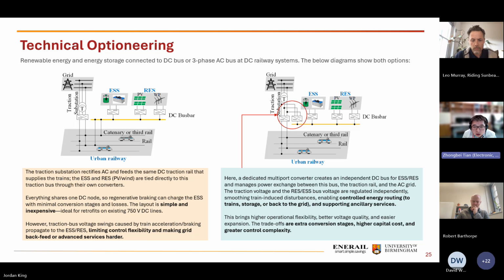The AC connection on the right-hand side can overcome this drawback, because the energy storage and renewable connect directly to the three-phase connection point, allowing the energy storage to engage with both the grid side and railway side. But the drawback is higher investment cost, because we'd need to update the existing railway traction converter, the rectifier, to a bidirectional converter to enable bidirectional power supply from the trains to energy storage.